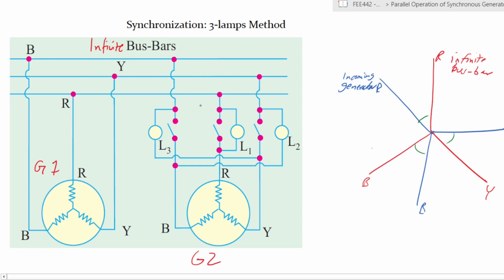So now if we look at how the lamps have been wired, this lamp 1 is connected between the red of the infinite bus bar and the red of the incoming generator. So lamp 1 is in between the two like that, right? Then you have lamp 2, which is connected between the yellow of the infinite and the blue of the incomer. Okay. Then you have lamp 3, which is connected between the blue, which is there, and the yellow. So it goes through here to the yellow, right?